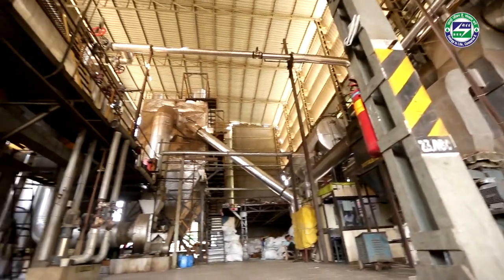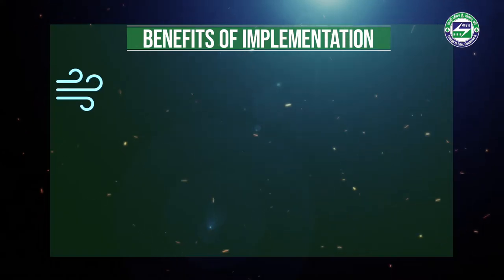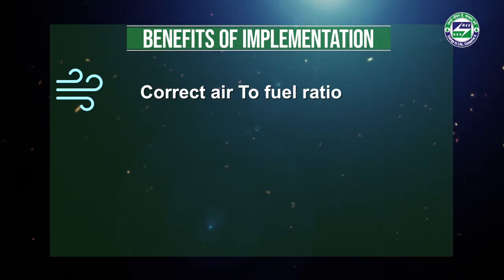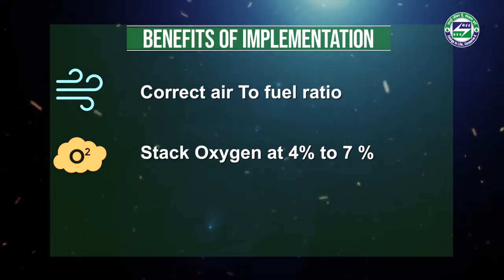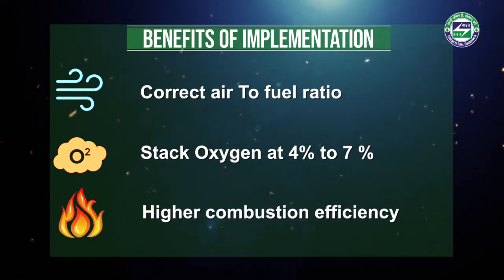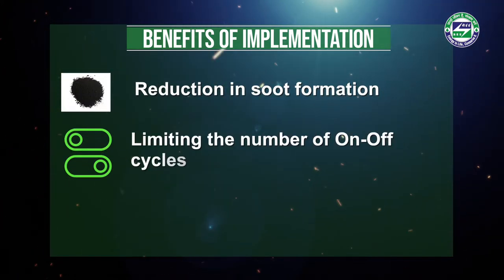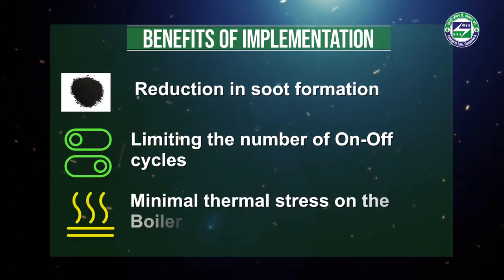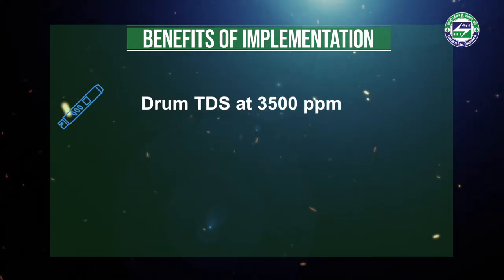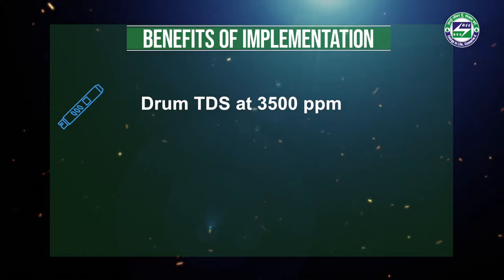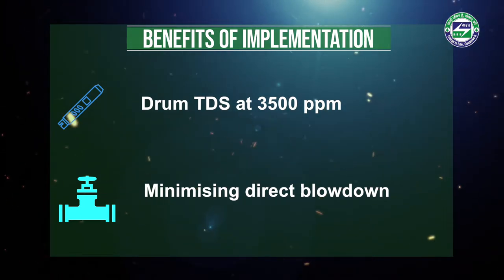The automation and control system provides many process-specific benefits: the correct air-to-fuel ratio is maintained, stack oxygen is maintained at the optimum level of four to seven percent, higher combustion efficiency is achieved, reduction in soot formation, limiting the number of on-off cycles, minimal thermal stress on the boiler, drum TDS maintained at an optimum level of 3,500 ppm, and minimizing direct blow down heat loss due to draining of blow down water.